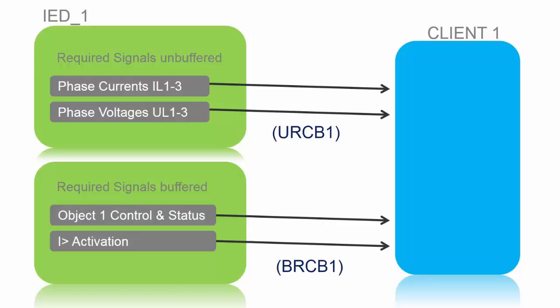For example, the first thing we will do is a vertical communication. So we will use the device name IED_1 and we will make a configuration that it will provide a client phase currents IL1 to 3 and phase voltage UL1 to 3 with an unbuffered report control block.